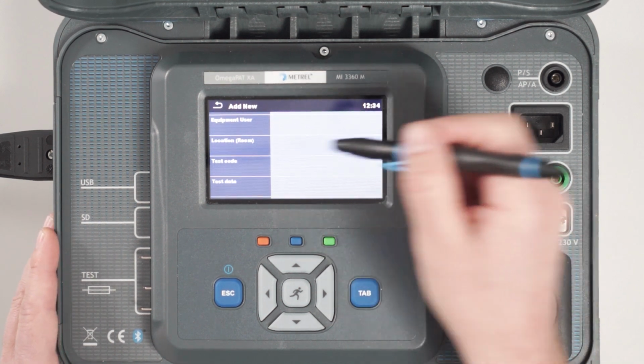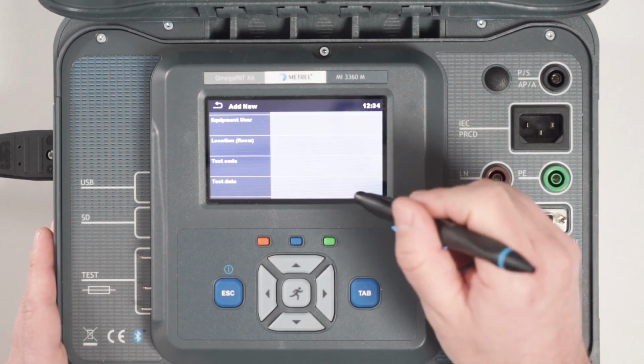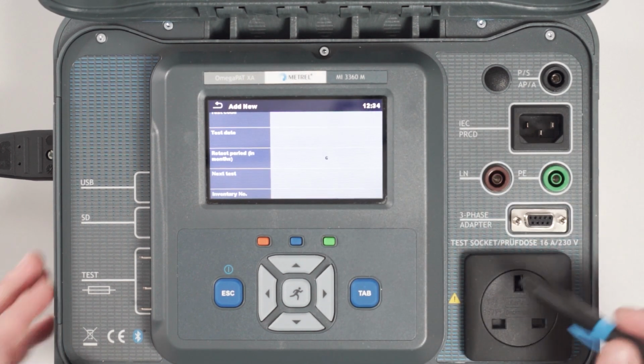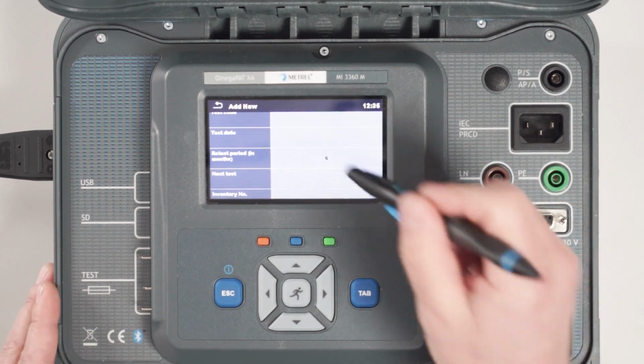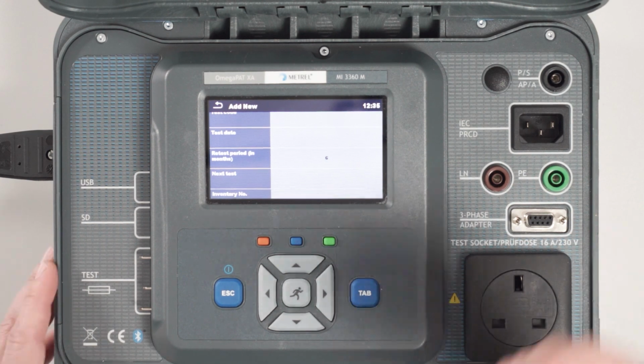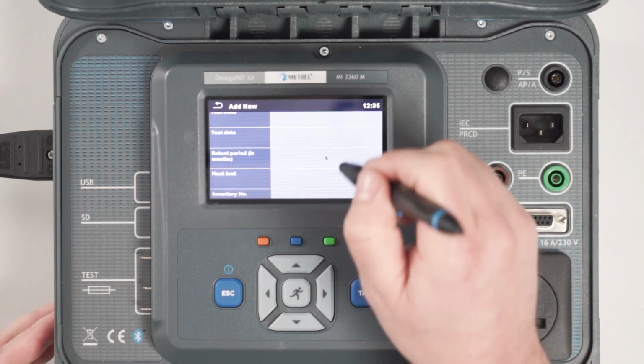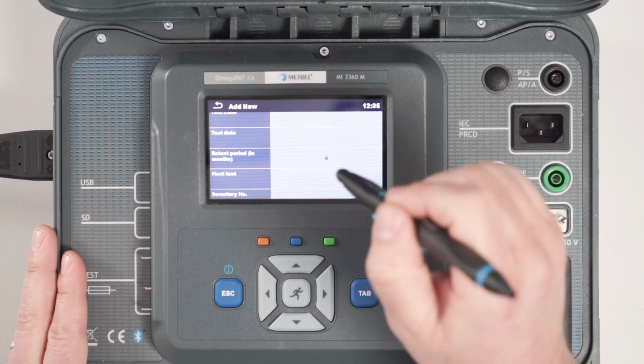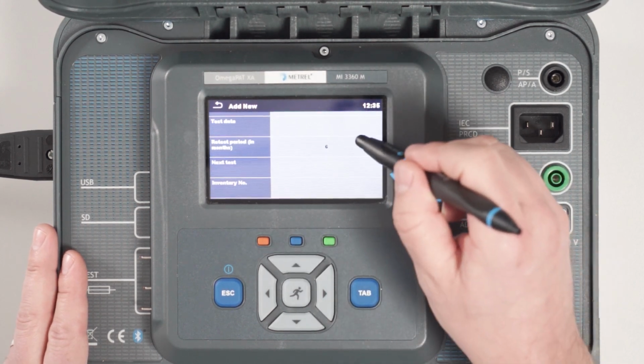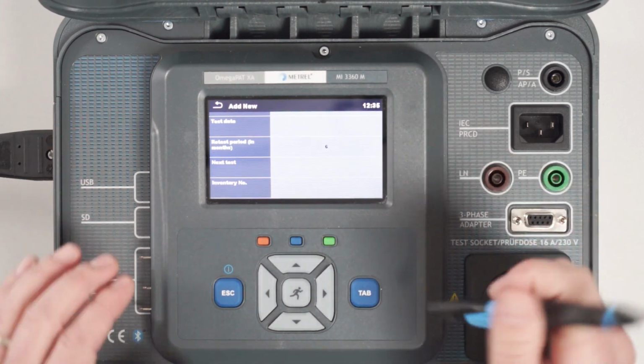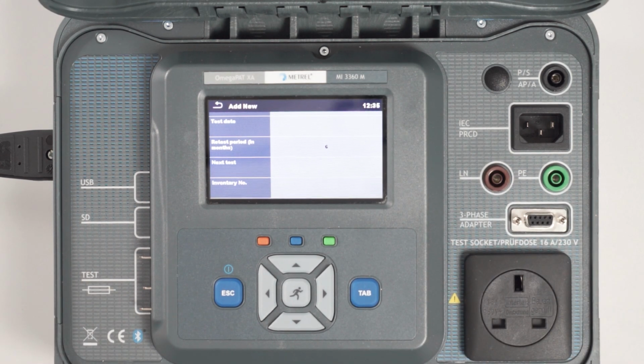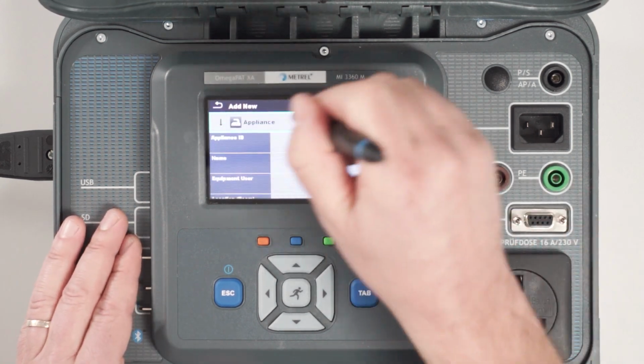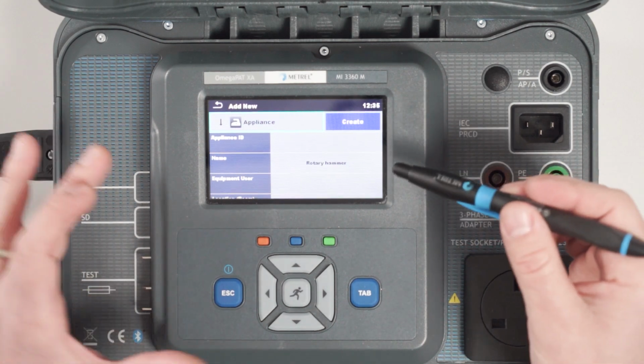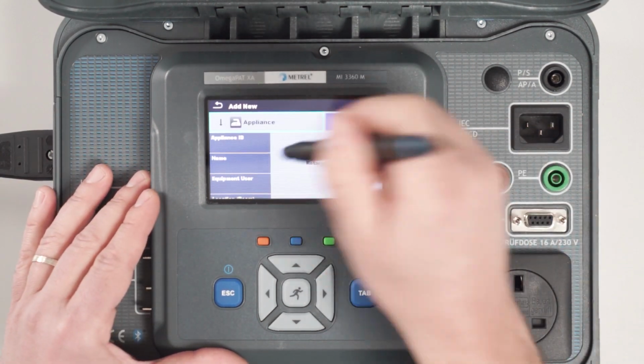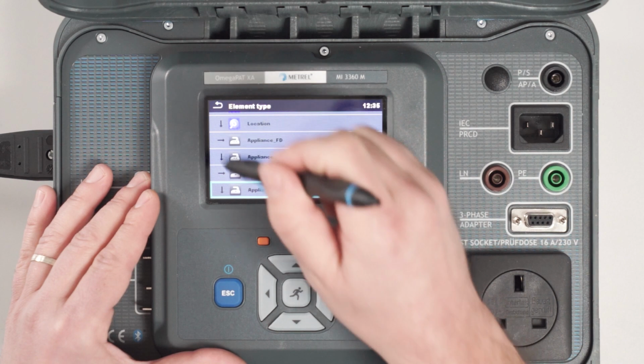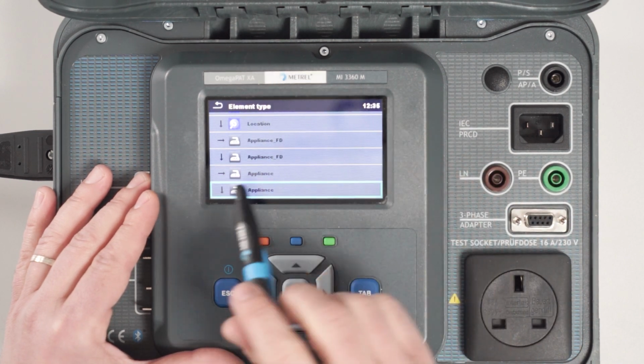Then we can additionally add the location of this appliance. We can add test code, test date, and retest period, and the next test will of course be automatically calculated based on the retest period given here in months. Additionally to these parameters, we can also add an inventory number if this is needed. These are the parameters available for the normal basic appliance.